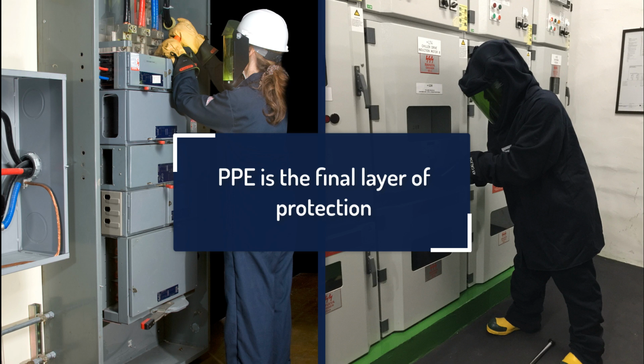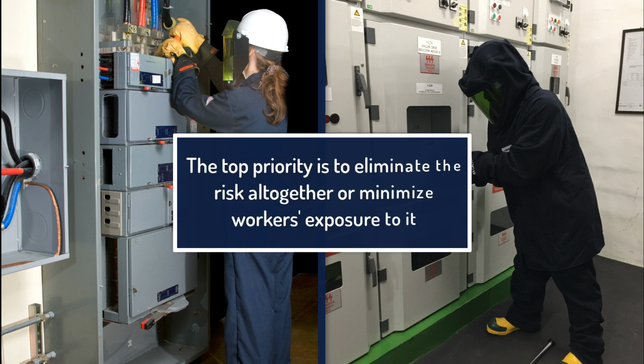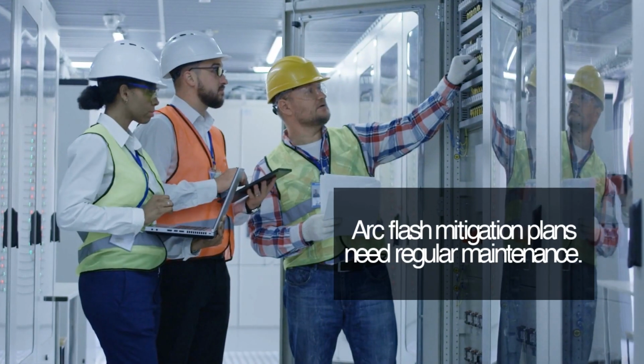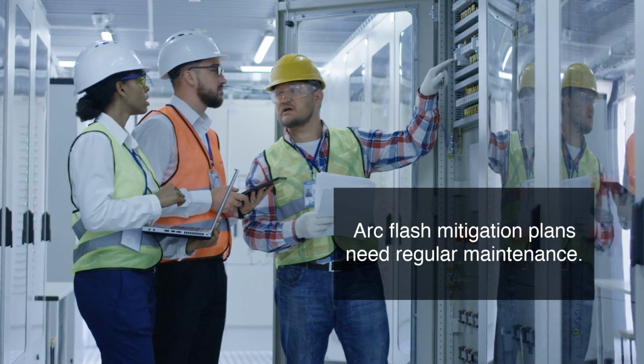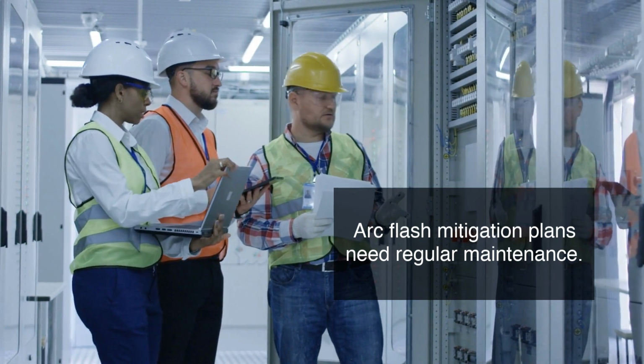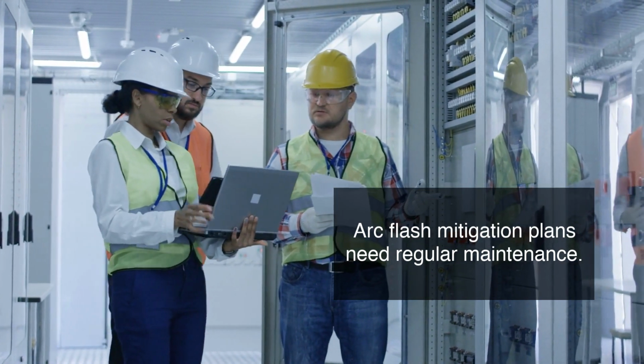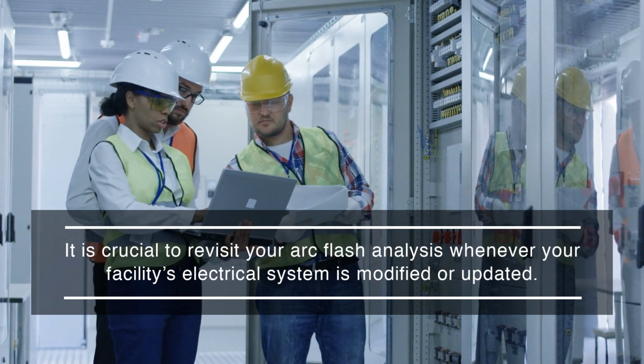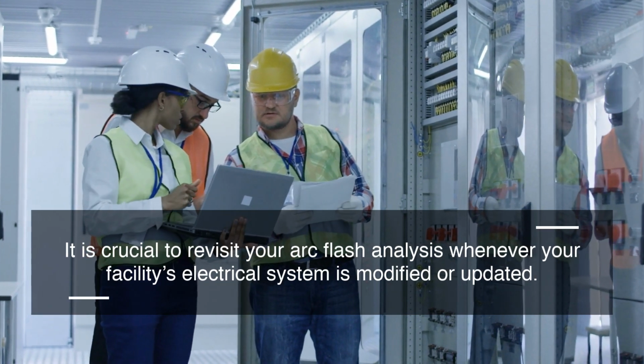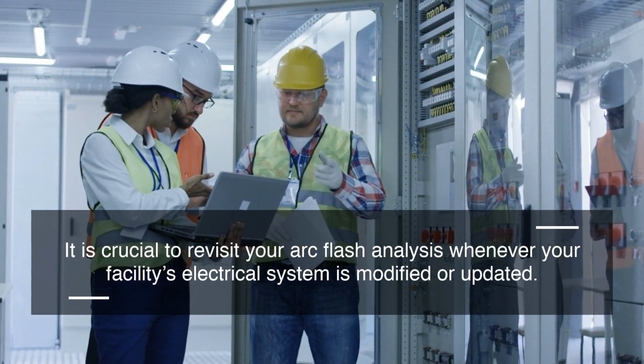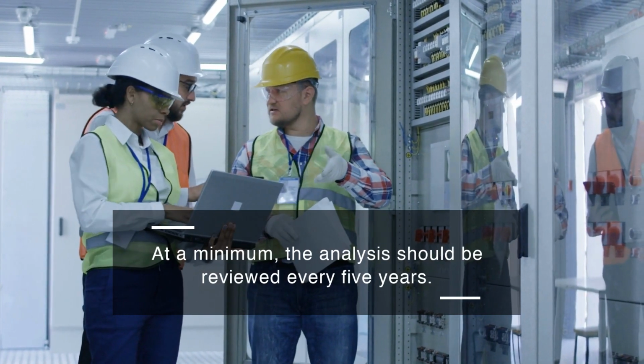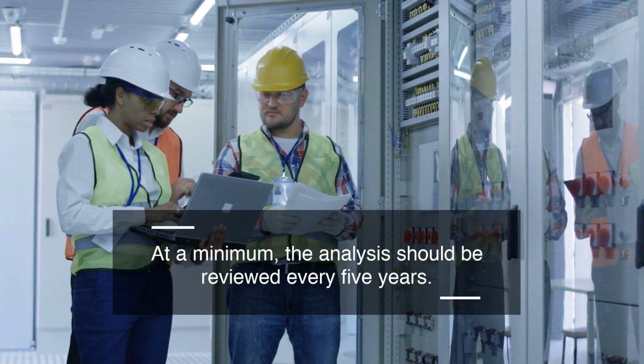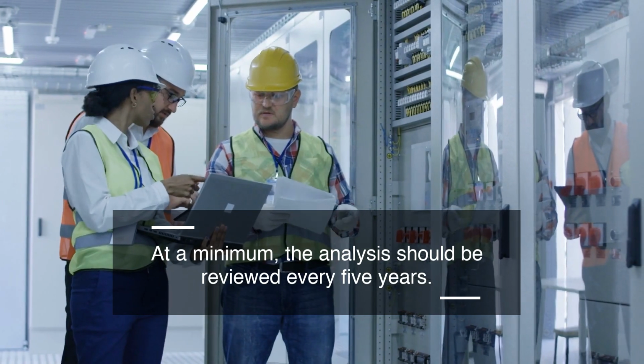More effective, and according to NFPA 70E, of top priority in mitigating arc flash risks is the elimination of the risk altogether, or minimizing workers' exposure to it. Just like anything else in your facility, your arc flash hazard mitigation plan needs regular maintenance. It's crucial to revisit your arc flash analysis whenever your facility's electrical system is modified or updated. At a minimum, the analysis should be reviewed every 5 years. Above all, communicate.